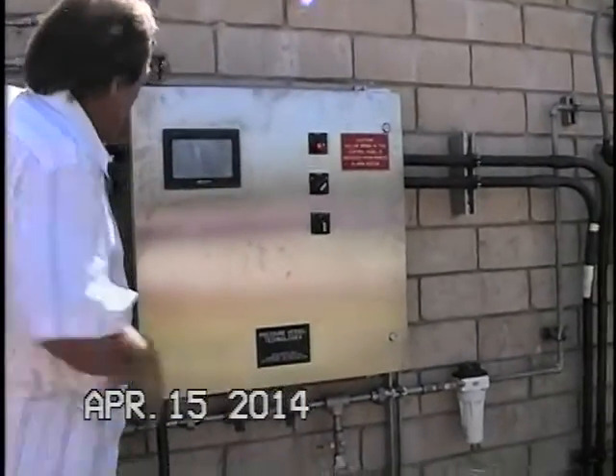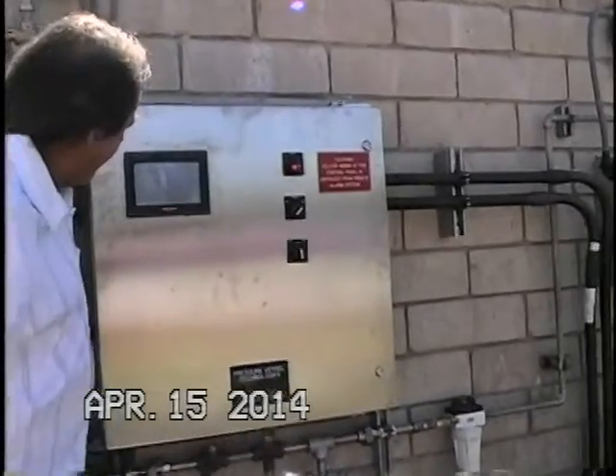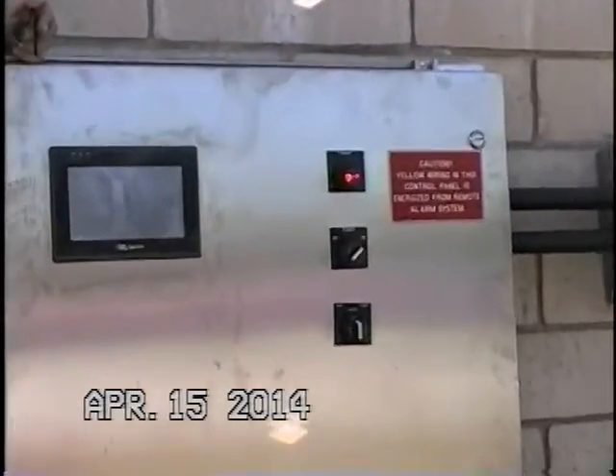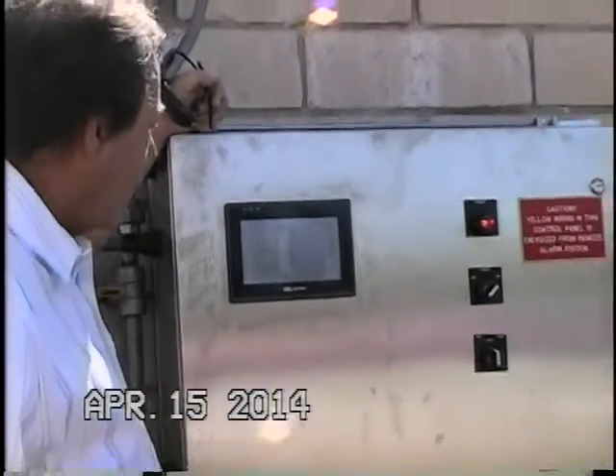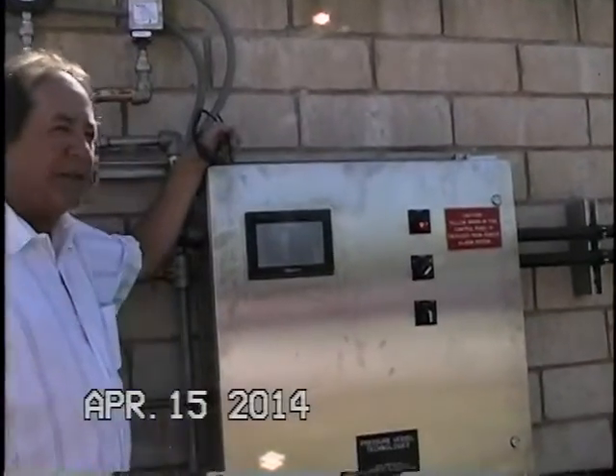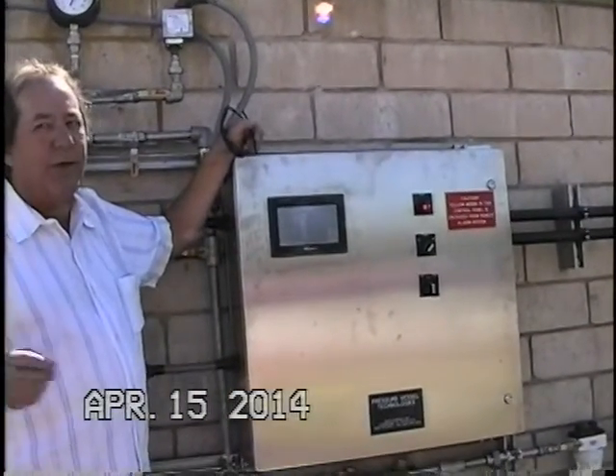Also on this side of the screen, you have your time delays. Remember we said we do not want to add air or vent air right away. Currently that's set at 5 minutes. That is also adjustable. It's as easy as going in here and touching the 5 minutes, putting 5 in there, a little calculator pops up, enter the values, push enter, and boom, there are your level set points. You can do that on your level set points and your time delays. That's one of the things I like about this: the adjustability is really, really good.